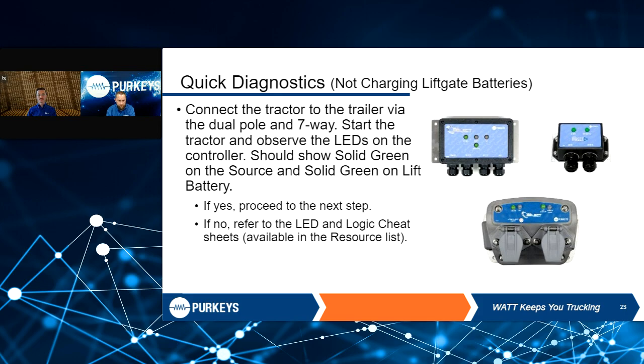In your resources, we have an LED and logic cheat sheet. It really walks you through all the different scenarios as far as the LEDs. But the key message to this slide is that any LEDs that are blinking, you're not charging. It is only giving you the current state of what your source and your liftgate batteries are sitting at. So say I'm blinking green on my source. That's just saying my tractor is above 12.4 volts, or my liftgate batteries are above 12.4. If you get the blinking amber light, it's below that threshold. Solid green is the only one indicating that charging is occurring.